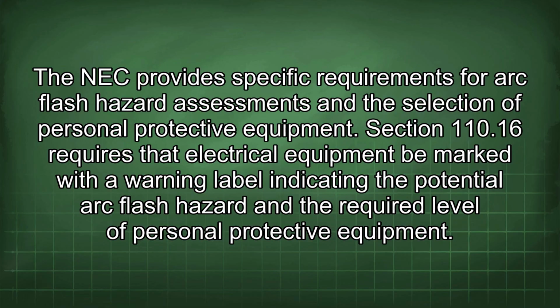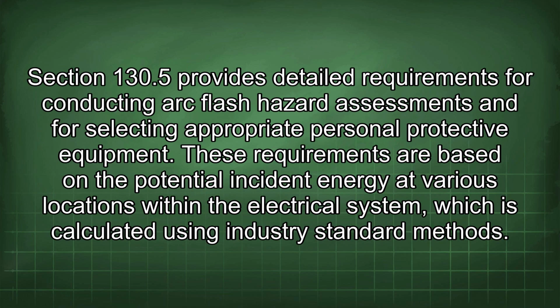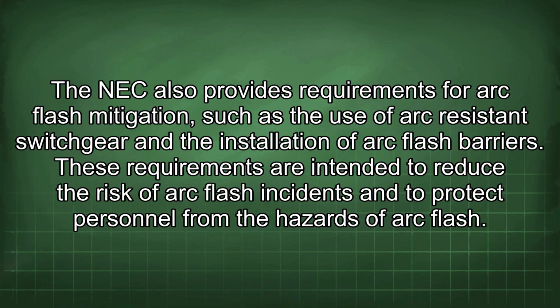equipment. Section 110.16 requires that electrical equipment be marked with a warning label indicating the potential arc flash hazard and the required level of personal protective equipment. Section 130.5 provides detailed requirements for conducting arc flash hazard assessments and for selecting appropriate personal protective equipment. These requirements are based on the potential incident energy at various locations within the electrical system, which is calculated using industry standard methods. The NEC also provides requirements for arc flash mitigation, such as the use of arc-resistant switchgear and the installation of arc flash barriers.